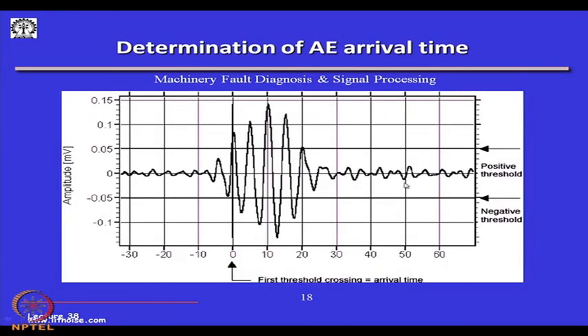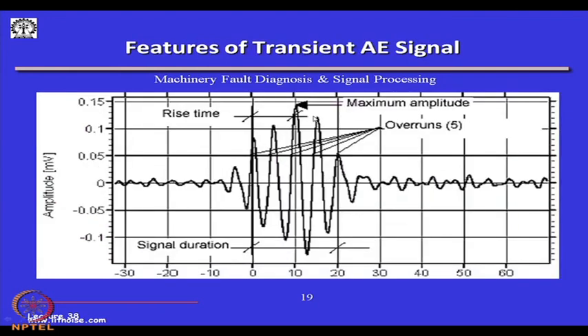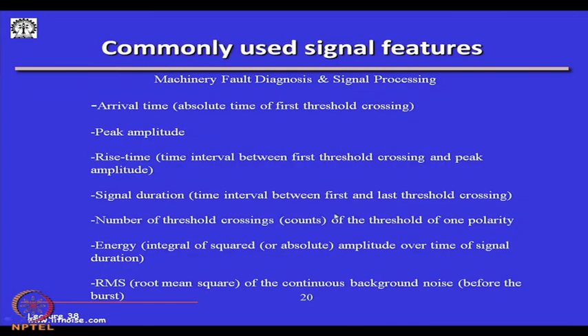We usually require a multi-channel system in machine structures so that by the method of triangulation we can find out the source of the acoustic emission. In the time domain, we can set many triggering events. For example, the number of peaks beyond a positive threshold can be used to quantify AE signals — including the first threshold crossing, the arrival time, maximum amplitude, number of overruns, and signal duration.